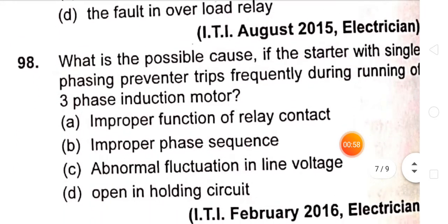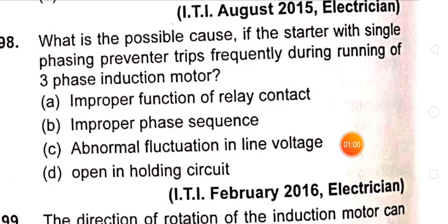What is the possible cause if the starter with single phasing preventer trips frequently during running of a three-phase induction motor? Abnormal fluctuation in line voltage.